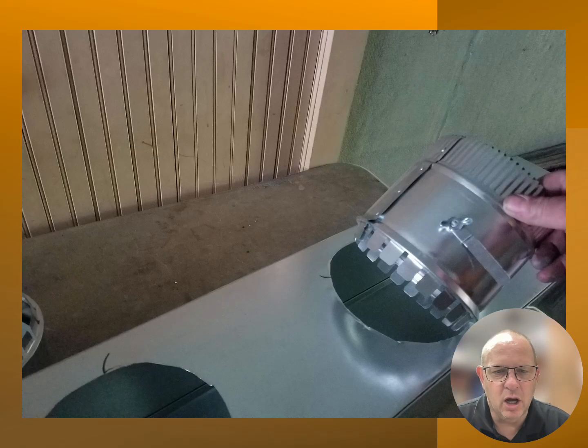I've cut both holes out in the ductwork, and you can see that I am going to insert this takeoff into that hole. Now, after I've inserted the takeoff into the hole that I have cut, those tabs that you see on that takeoff, I am going to bend them against the metal on the ductwork, and that's going to hold that takeoff in place. You might want to put some screws in there as well, although you need to be careful that you don't screw one of the sheet metal screws into your fingers, because getting those tabs over and a screw in them is going to be very difficult, as flimsy as they are. But you should end up with a nice tight connection on that system.